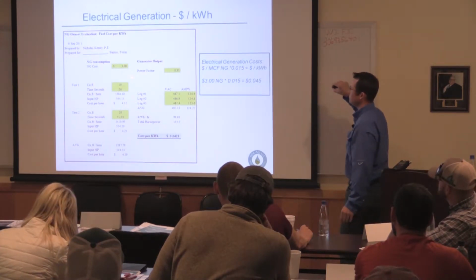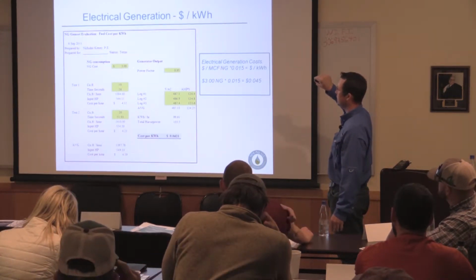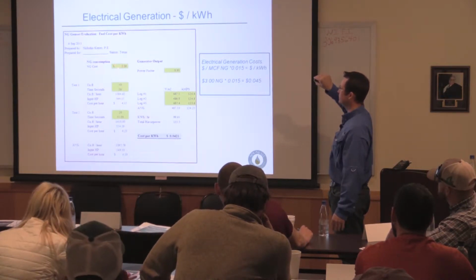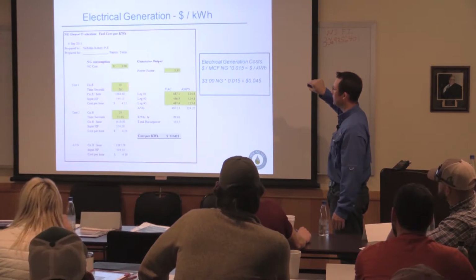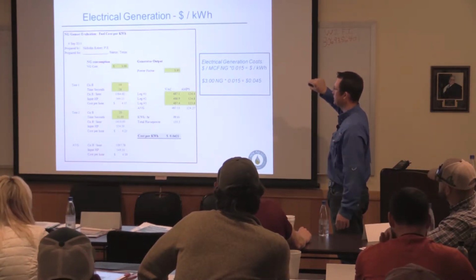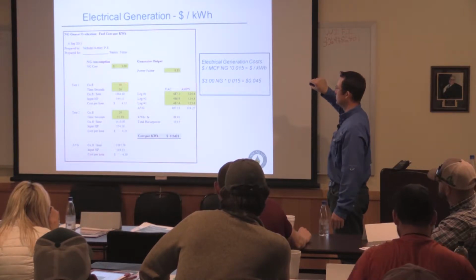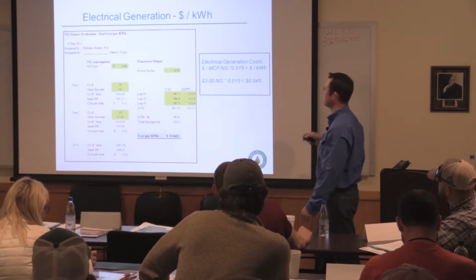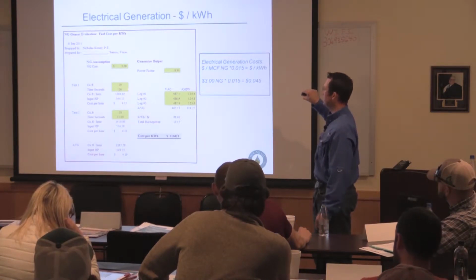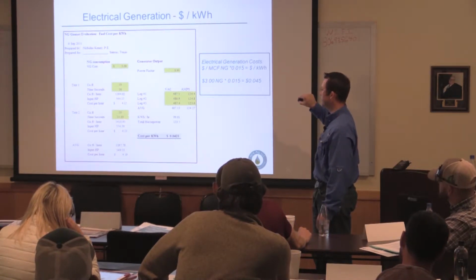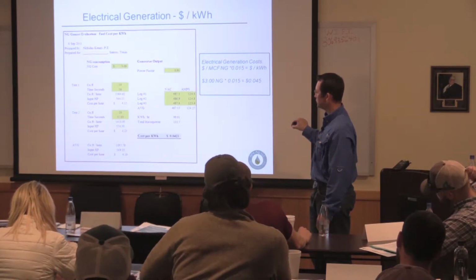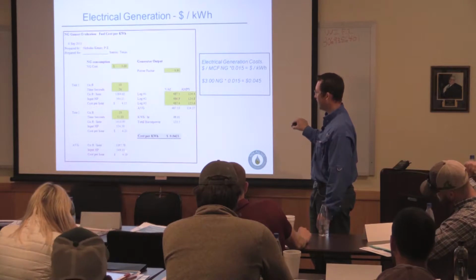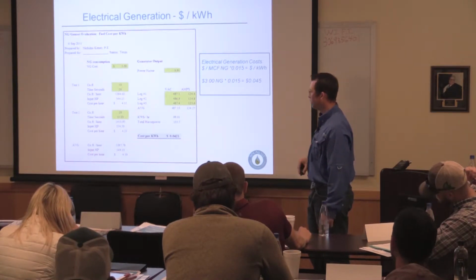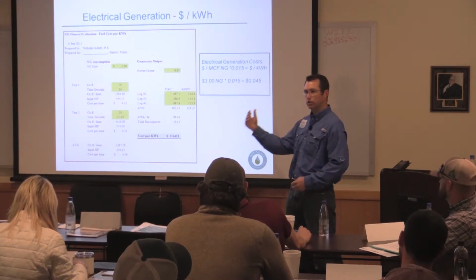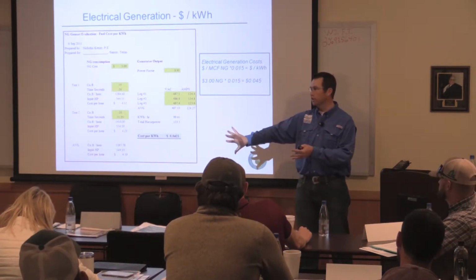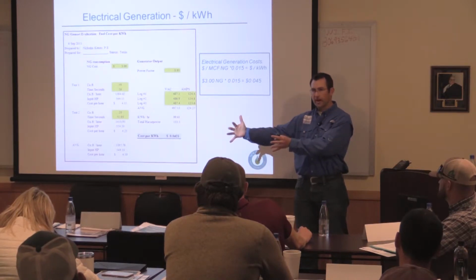So following through here, we look at this $3 natural gas cost. At the time it was $4.50 and it still made sense. We measured the fuel coming in with a stopwatch on a Roots-style gear-driven gas meter: 10 cubic feet in 26 seconds, and 20 cubic feet in 51.03 seconds. Averaged out, it was using just shy of 1,400 cubic feet per hour at a cost of $4.19 per hour. That's the fuel cost per hour to run this genset at this particular loading, the input side.